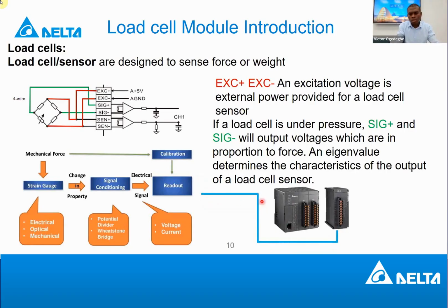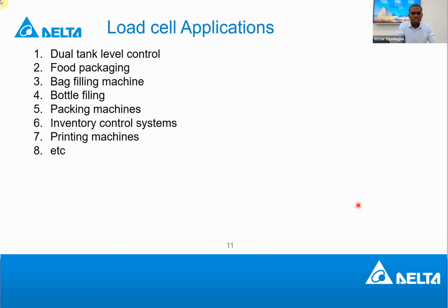So this is what happens. It goes to the load cell module, and the load cell module has an analog to digital converter. With that converter, you calibrate that very signal. What comes in here is an analog signal, so you calibrate it to give you a very smooth digital value. And that digital value you use to operate your machine.